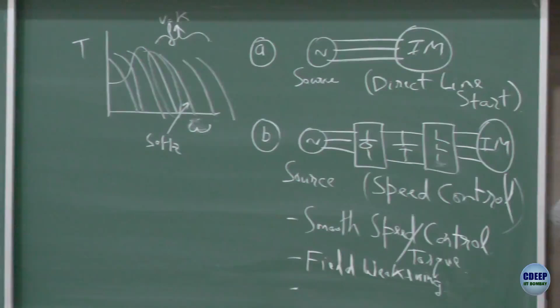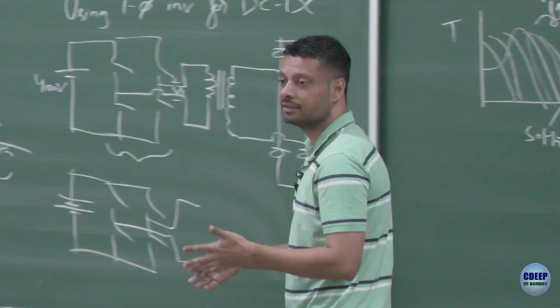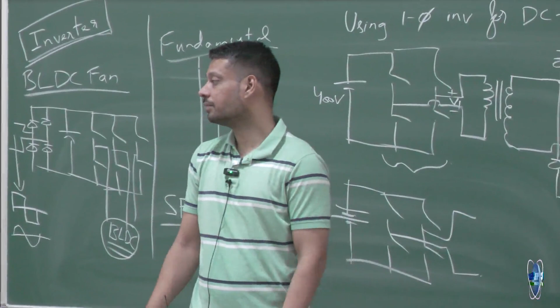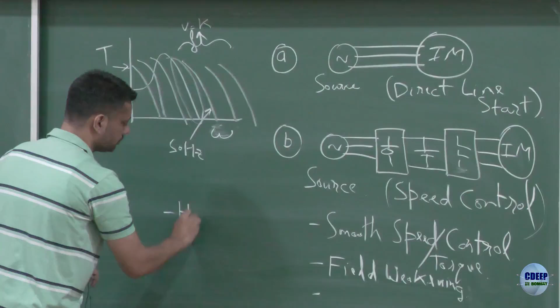Go ahead, recall what you did in the experiment. There was one part where it wasn't about measuring something, but about directly getting a sense of something, not watching the oscilloscope or meter but feeling what's happening yourself. That was starting torque. In the direct line start case, the starting torque is limited. If you do V by F, you can have a much higher starting torque.